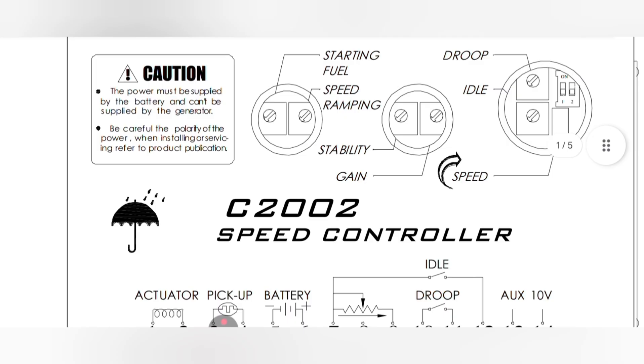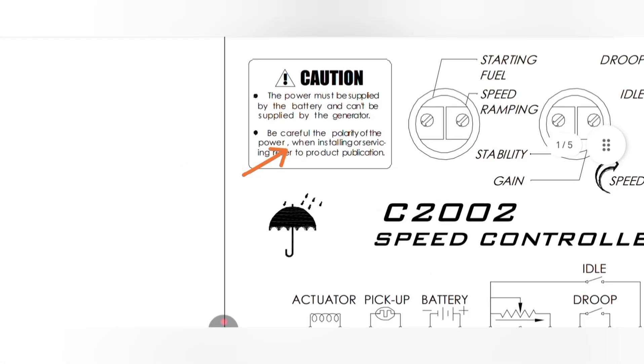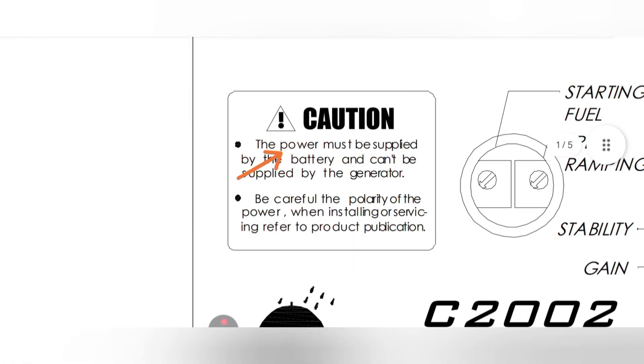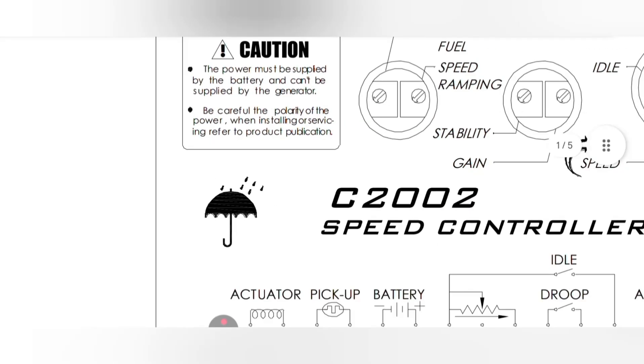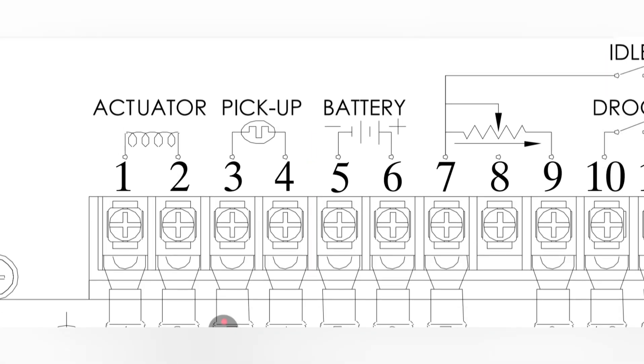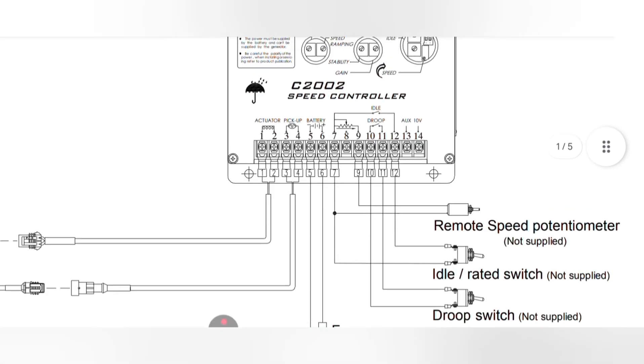Important caution: power must be supplied from the battery only — it cannot be supplied from the generator's charging alternator. Connect battery pins five and six directly from your battery. Be careful to observe polarity when servicing: connect negative to negative and positive to positive, because this is a DC system. Incorrect polarity will blow the controller.